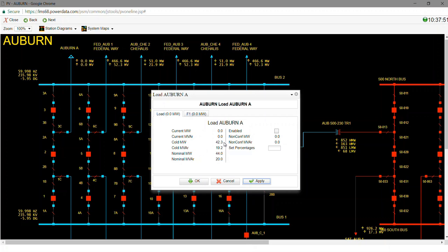In the simulator, when you bring loads back in, you will not see the initial inrush of energizing compressors and things like that, but what you will see is the dynamic effect of the returning load diversity over time. So as you bring back portions of feeders, you will see they will be brought back at a higher value, and you will see that taper off. So the longer this feeder is de-energized, the more this cold load value will build up.